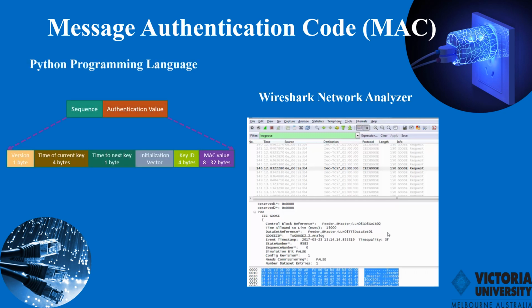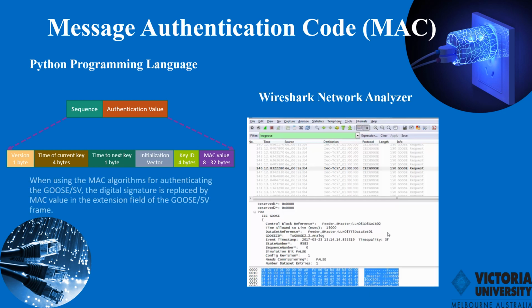The MAC value authentication will be written using a Python script. It will contain the data and code for secret key generation. When using the MAC algorithms for authenticating GOOSE and SV, the digital signature is replaced by the MAC value in the extension field of the GOOSE SV frame. So the total bytes of the GOOSE message will increase.